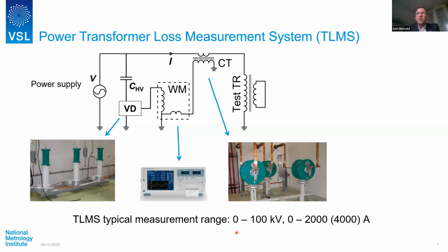So this is the system that is actually used by the power transformer manufacturer to verify his product. And of course, he is not allowed, as a butcher, to check his own meat. So when he is doing this calibration, often the utility that is purchasing the power transformer is witnessing the measurement in order to verify that the measurement is really done correctly and that the numbers on the test report are really reliable.